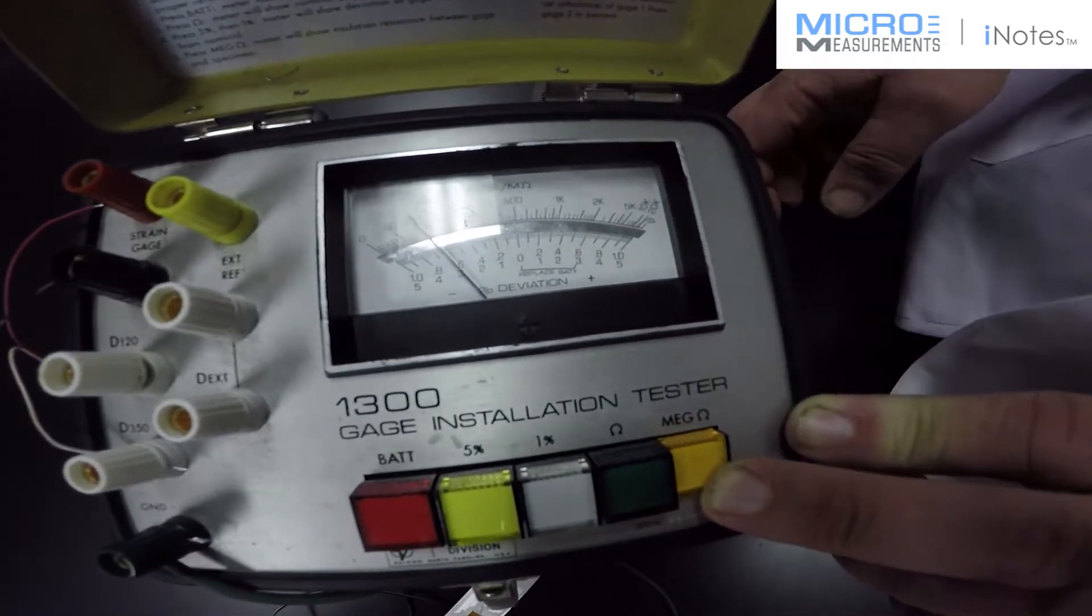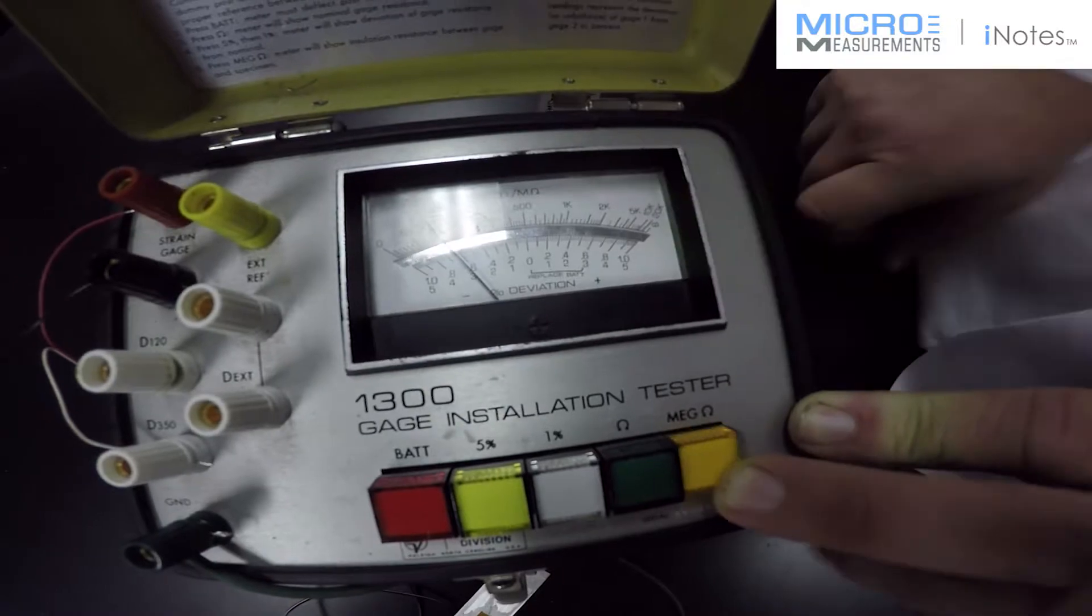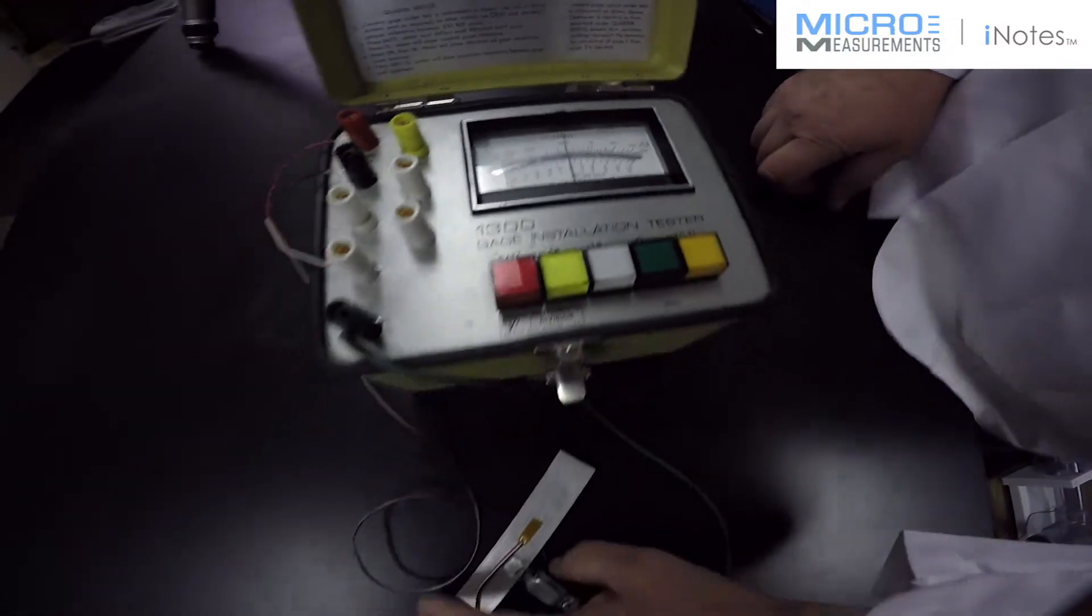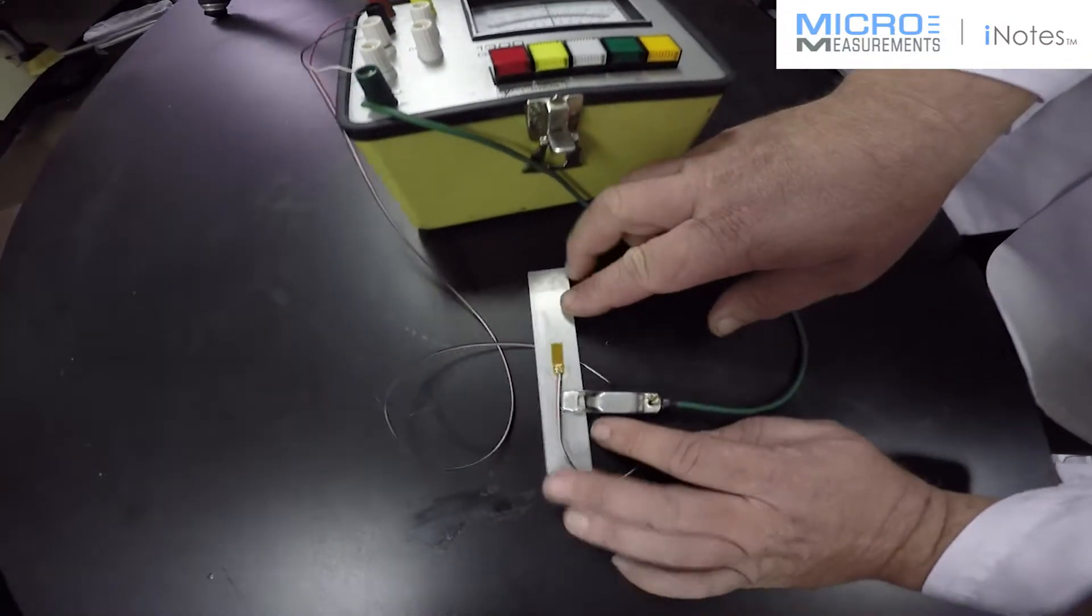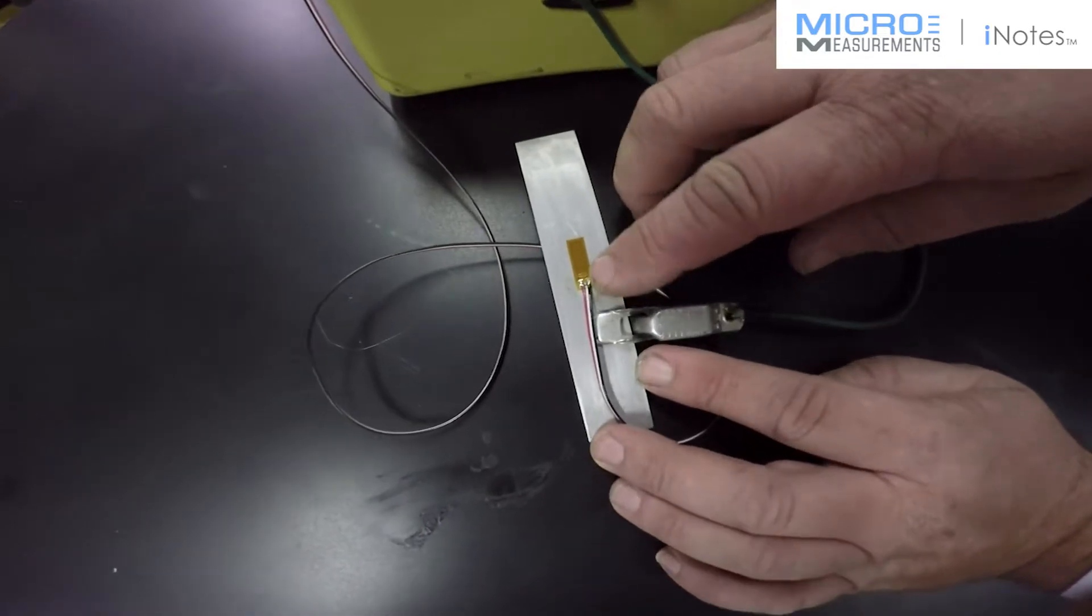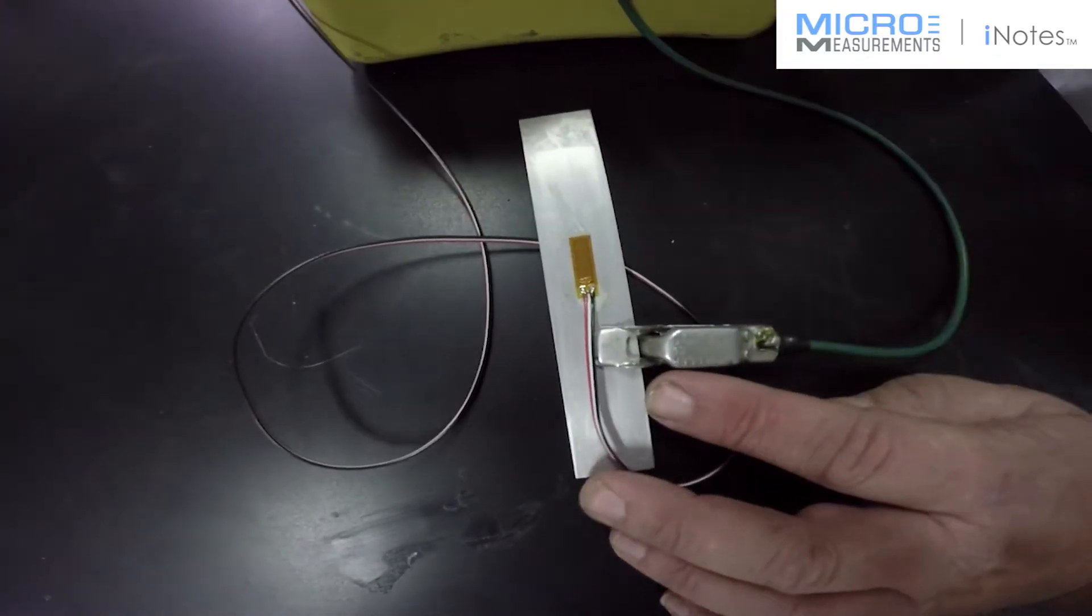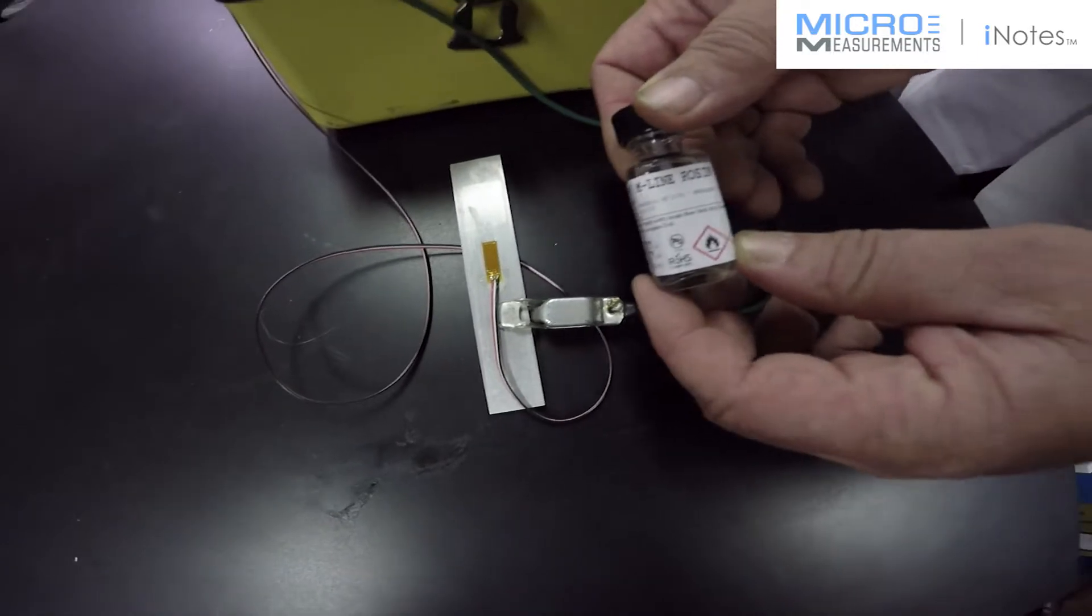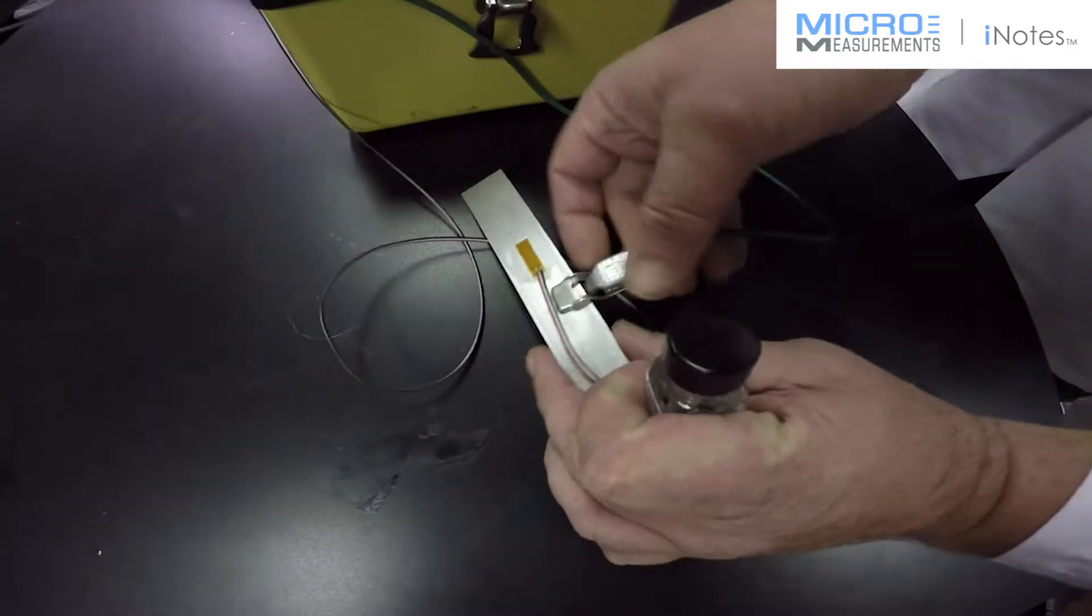So the problem that you typically have when you have a low resistance to ground is flux. And in fact, I have left the flux on here. After soldering, I did not go back and use the Micro-Measurements rosin solvent to clean that up. So let's go ahead and clean this up a little bit and we'll see what difference that makes.